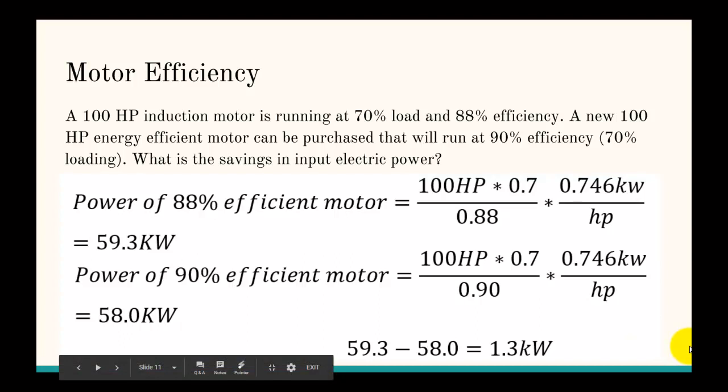Let's first look at a motor efficiency problem. A 100 horsepower motor is running at 70% load and 88% efficiency. A new 100 horsepower energy efficiency motor can be purchased that will run at 90% efficiency at the same 70% loading. What is the savings in input electrical power? This one's relatively easy. The only trick is that you want to make sure you take into account how much it's loaded, so that's what the 0.7 is here.